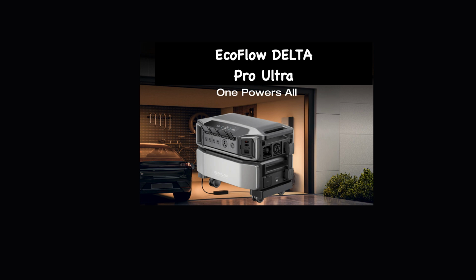This unit is not driven by gas or diesel generation but uses the battery storage unit that is charged when the utility is available. This means that the unit can be placed indoors or outdoors and is virtually silent when operating. It has a stackable design that can be expanded to increase output in only minutes. Compatible with various energy sources, from solar to gas, to meet your ever-changing power needs.